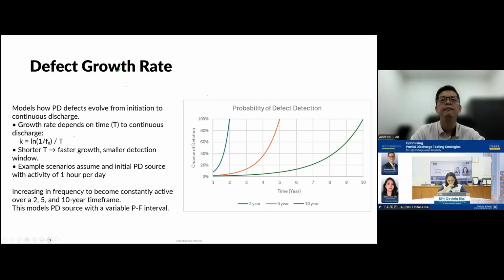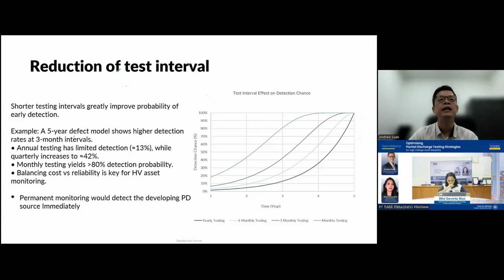Since the defect timeline varies from 2 to 5 to 10 years, we definitely want to detect it as early as possible. That brings me to the next point: how early do I want to detect this PD? On the graph, the first line is yearly testing, the light blue one is 6-monthly testing, the purple one is 3-month testing, and the green one is monthly testing. Based on this we plot the chart and get the probability.